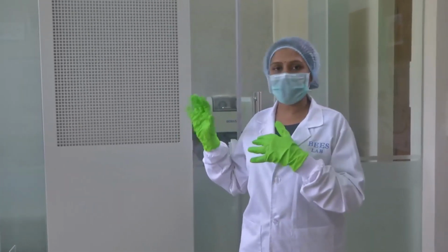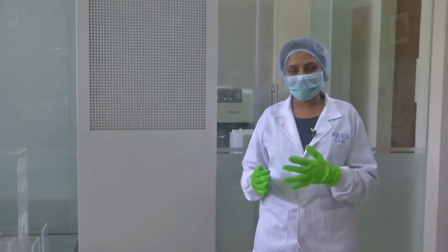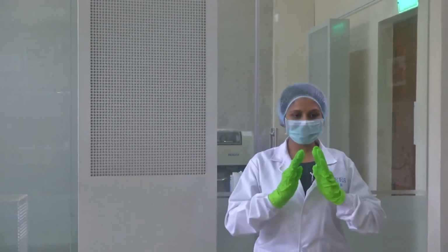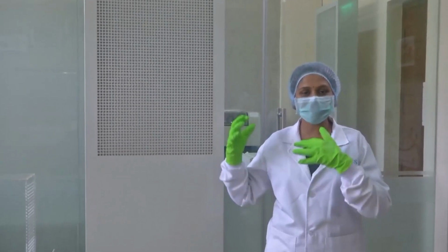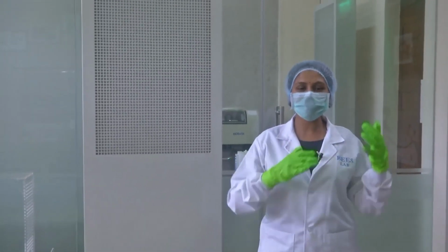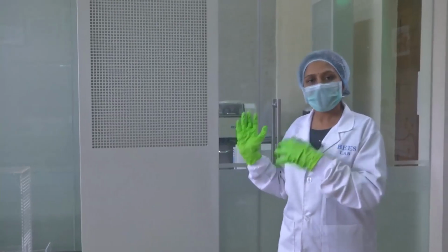So, how these HEPA filters work is 50% of the atmospheric air is taken in, and 50% of the air which is inside, the clean air, is always recirculated within these filters. When you are talking about recirculation, assume I am going to maintain this clean room at perfectly clean levels. The amount of energy that the entire HVAC system takes, the load on the system reduces, provided you put your efforts in maintaining the clean room by following these procedures, reducing the particulate count. So, by following these procedures, you could reduce the load on the HVAC system.